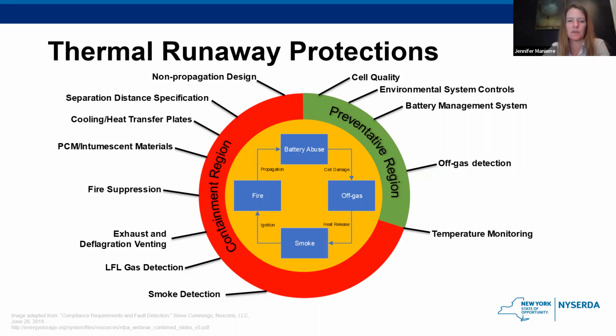Lithium ion batteries do not release flammable gases as a normal course of their charging and discharging, but when something goes wrong and they start to overheat and catch fire, at that point, they actually can start to emit those types of gases. So we want that sort of gas detection in there. Exhaust and deflagration venting systems, fire suppression systems, you get the idea. We're just working around, if this thing fails, the next thing covers it, and so on. And I think this chart, in my opinion, summarizes all of the safety features that are incorporated into the New York State Fire Code now, which is great because they are all good things.